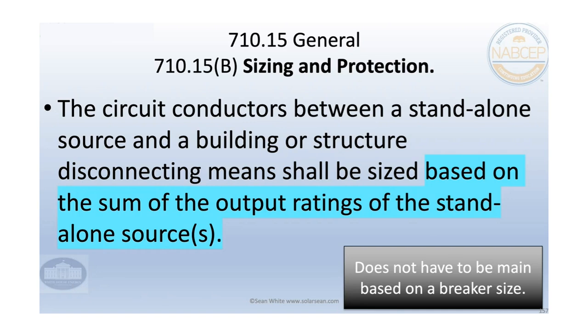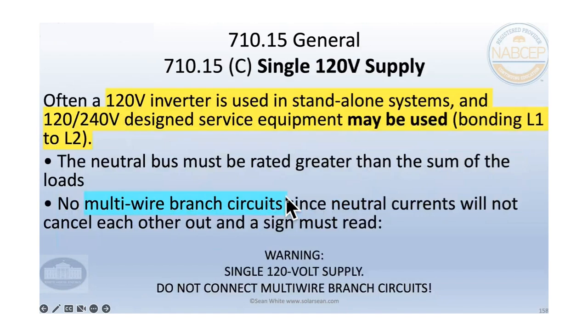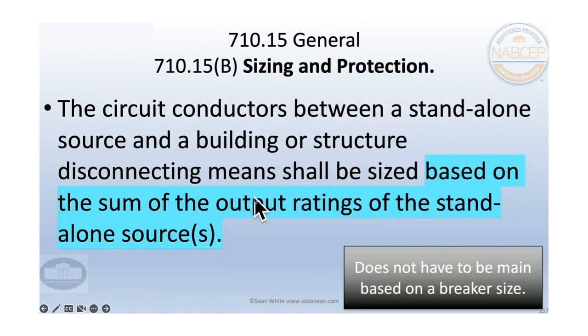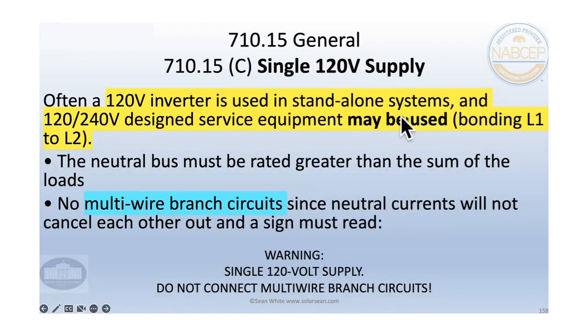We'll talk a little bit about that more if we have more time. So we size things on the continuous currents and just obvious things here. One of the things too that you see with standalone systems is a lot of times they'll be able to supply only 120 volt loads, and people will take a 120/240 equipment, bond line 1 to line 2, and then you could overload the neutral if you use a multi-wire branch circuit.